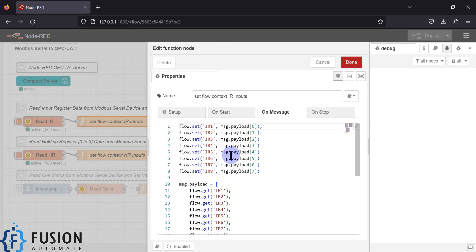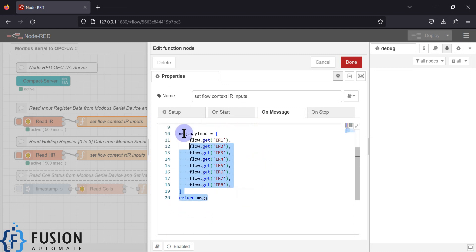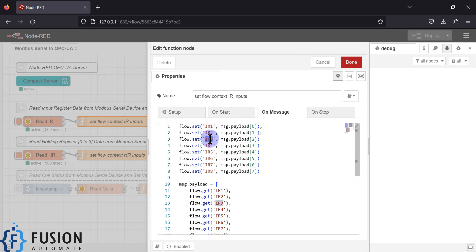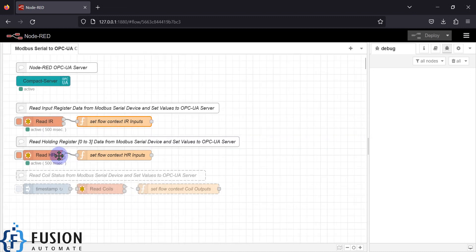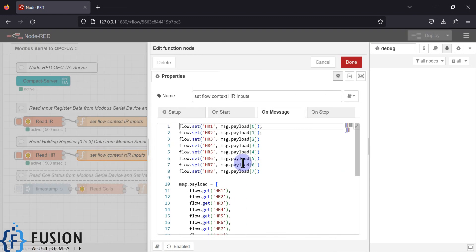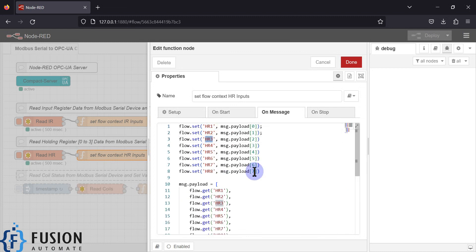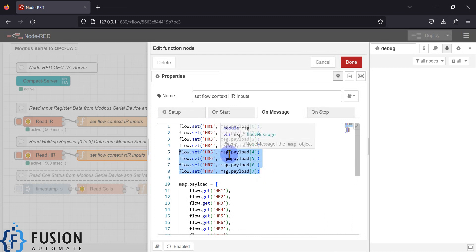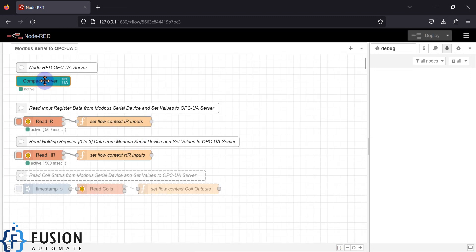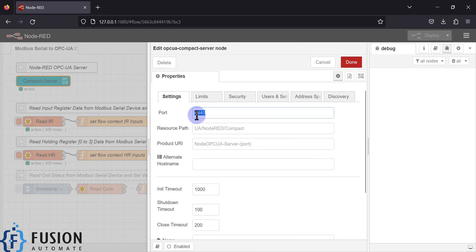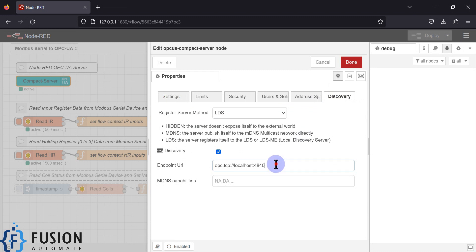Whatever data I am getting, I am setting those as flow variables. You can see flow.set 'ir1' and whatever payload I am getting from this node — input register 1 will be msg.payload[0]. This is how I'm setting input register 1 value, input register 2 value, input register 3 value, and so on. Then the same thing is done for holding registers — reading and setting holding register 1, 2, 3 values. You can comment out the ones you're not using, but leaving them is fine too. Now we will look at a few things about this Compact OPC UA server node.